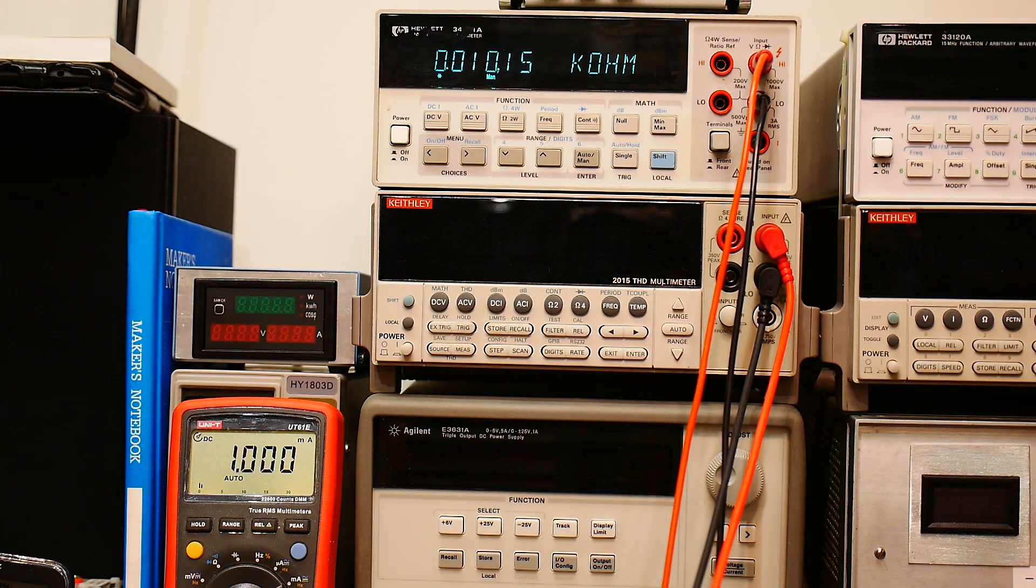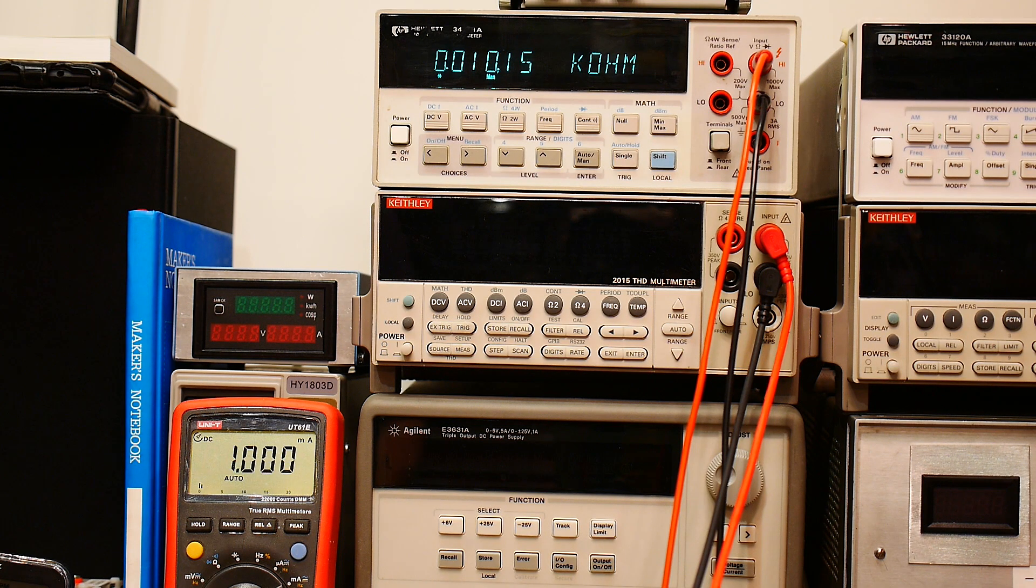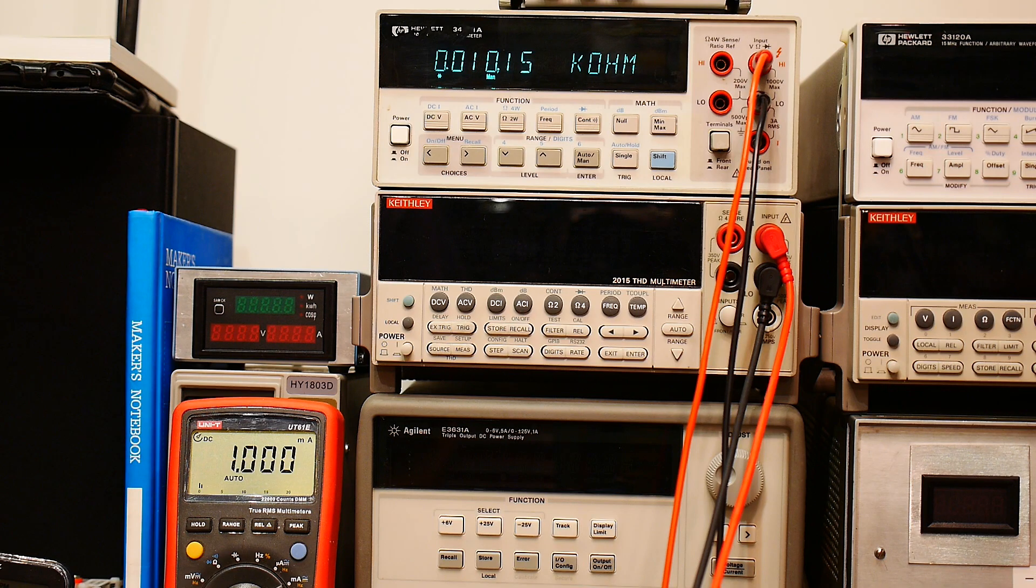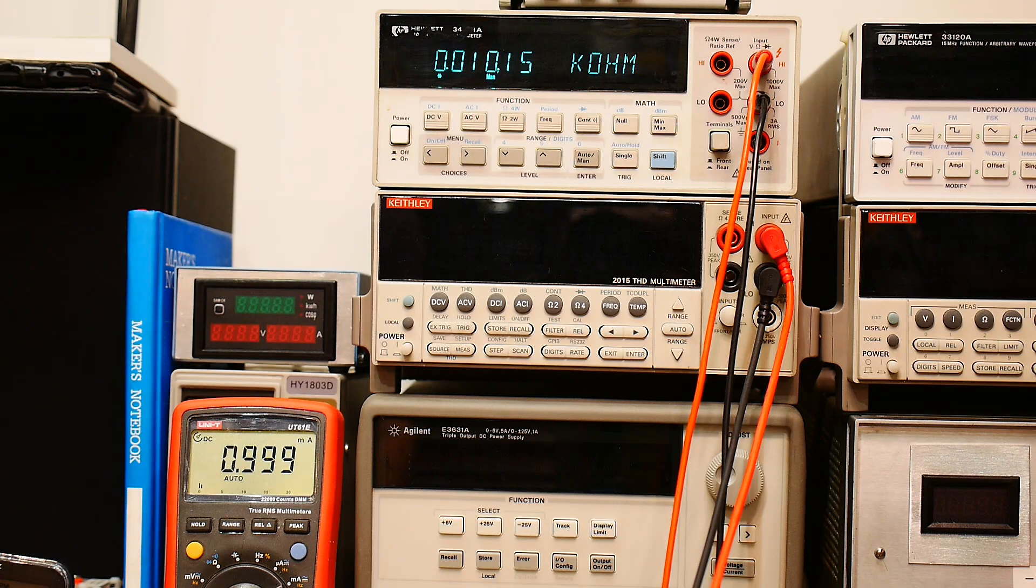Now how does something measure ohms? It forces a current and measures a voltage. So here it's forcing exactly one milliamp, and this is a pretty high precision box, so it's outputting a pretty precise one milliamp.